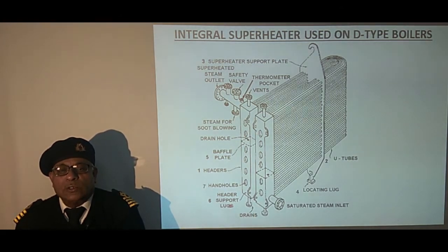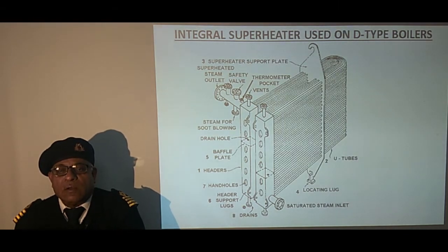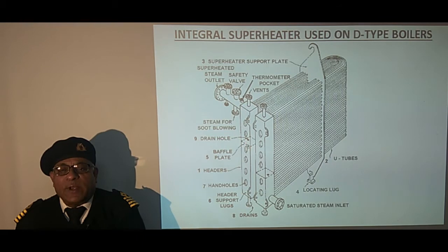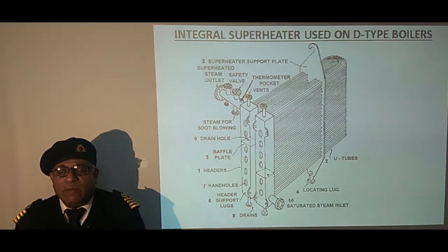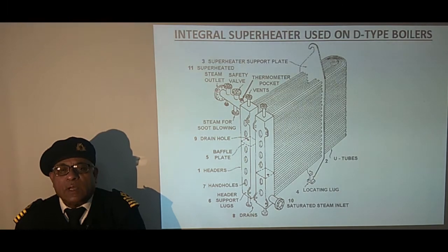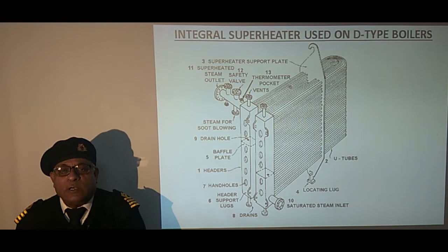Then we have handholds opposite the tubes to get access to the internals. Then we have drains on both headers. Then we have a drain hole in the baffle plate so that condensate can go to the bottom and be removed from the drains. Then we have the saturated steam inlet at the bottom. We have the superheated steam outlet at the top. We have a safety valve, a thermometer pocket, and a vent on each header.